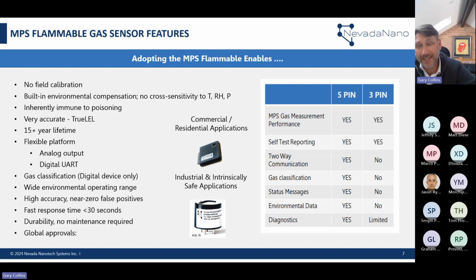But because we understand the density of the different gases, we can do forms of compensation or use a K factor internally to provide extremely accurate measurements, i.e. plus or minus 10% across the whole temperature range, which is why we use the term true LEL on our flammable devices. I've touched upon the 15 years life and that we offer an analog and digital output. I'll come on and talk about that in a bit more detail, because if you're looking for an analog sensor, we will give you a specific voltage range of say 0.4 to 2 volts, but there is also the ability to change that scale to meet your needs so your circuits don't have to change.